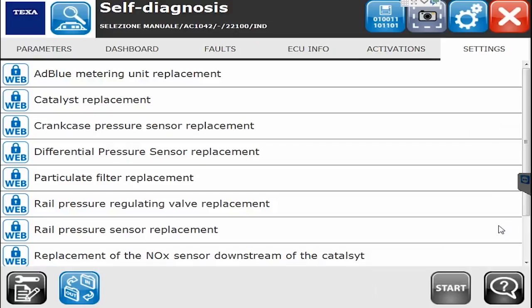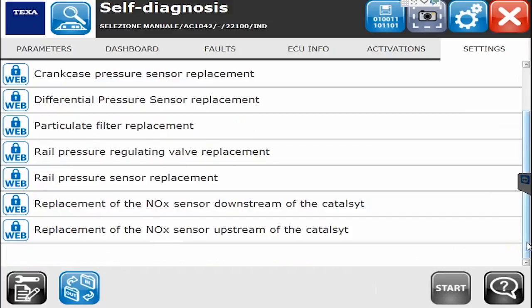The Settings tab has a lot more commands you can run as well — for example, when you replace sensors, you have to run certain commands. The ones that say 'weblock' mean two things: one, you need to sign a release form one time with TEXA, and two, you have to be on the internet to run those commands. So again, this is very quickly a 2016 FPT engine on a 2016 Link Belt. Thank you for watching.